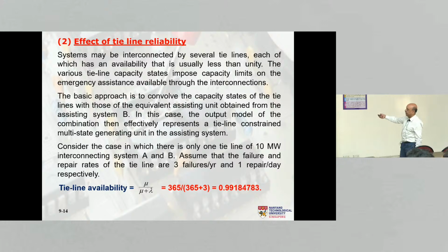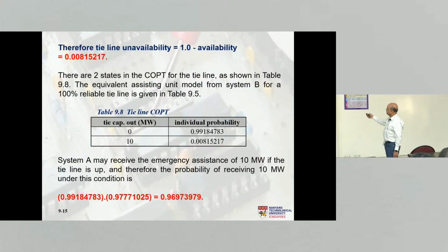Assume that the failure and repair rate of the tie line are 3 failures per year and 1 repair per day. So what is the availability? Mu over lambda plus mu. Mu is 1, lambda is 3. So you can calculate using this. Mu is given here, 1 repair per day, so it is 365 repairs per year. So you have to use that number and you will get the availability.